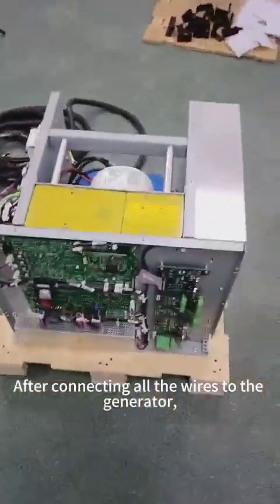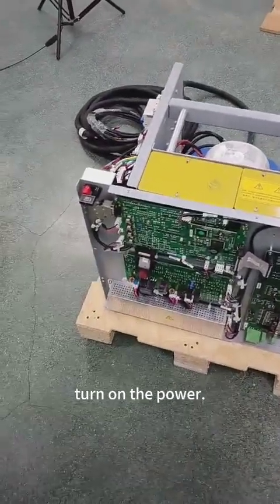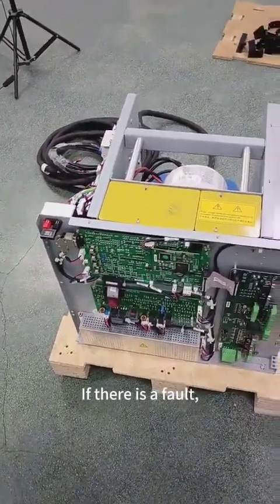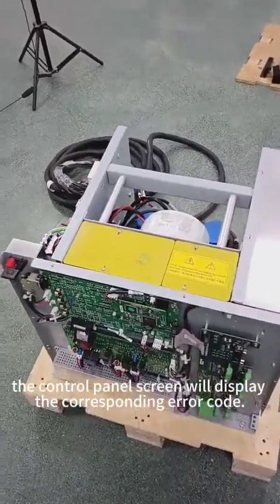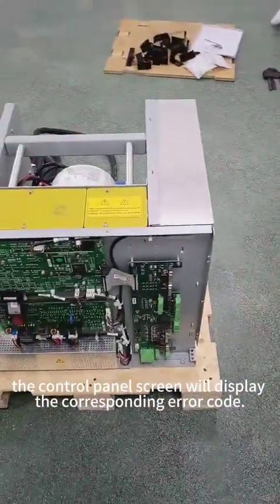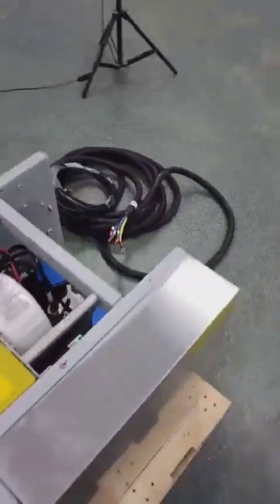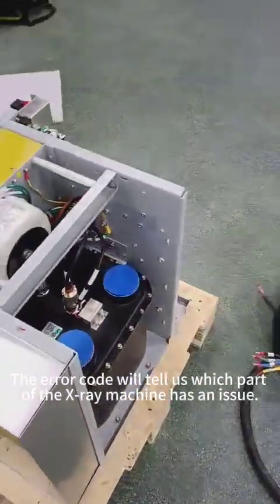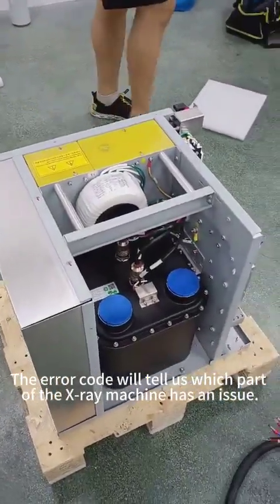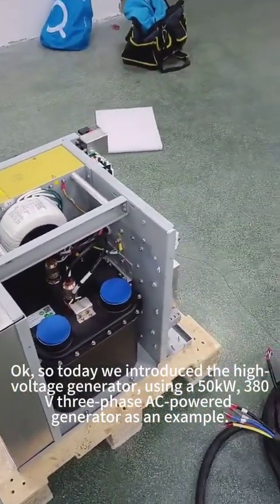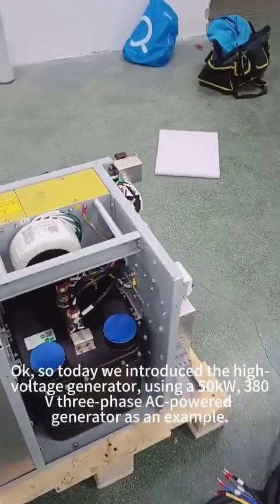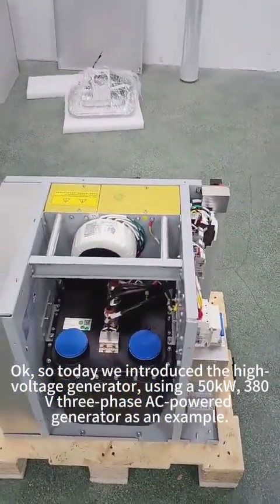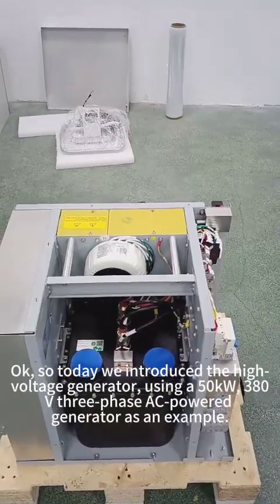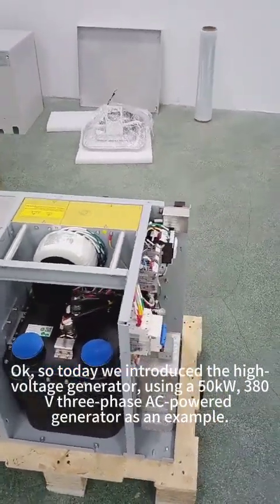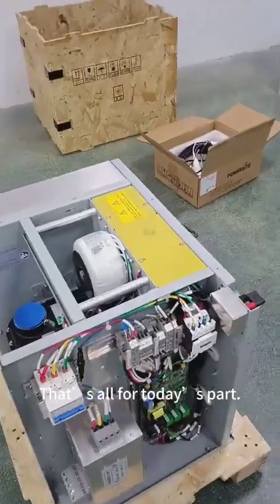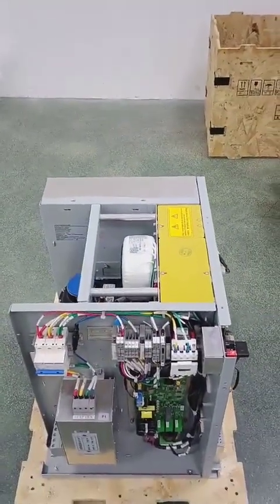After connecting all the wires to the generator, turn on the power. If there's a fault, the control panel screen will display the corresponding error code. The error code will tell us which part of the X-ray machine has an issue. Okay, so today we introduce the high voltage generator using a 50 kilowatt, 380 volt, 3-phase AC powered generator as an example. That's all for today's part.